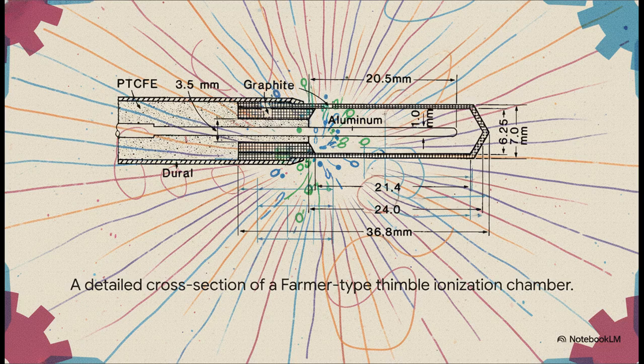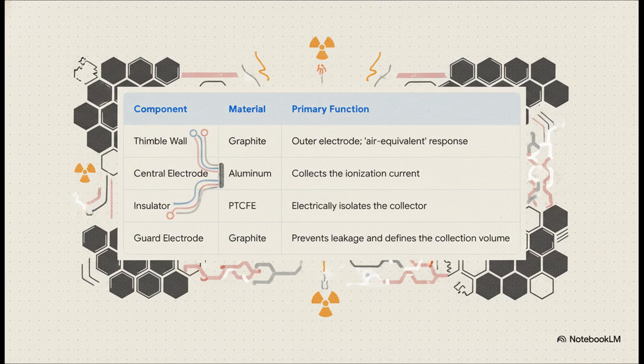And here it is. This is a classic farmer-type thimble chamber. You'll find these in hospitals all over the world, and it's a perfect example of everything we've just talked about. You can see all the parts: the outer wall, or the thimble, the central collecting electrode made of aluminum, and then nestled right in between, the crucial insulator and guard electrode assembly that makes the whole thing work. So let's do a quick rundown. You've got the thimble wall, usually made of graphite because it's air equivalent. It responds to radiation just like air does. Then there's the central electrode, made of aluminum, designed purely to collect that tiny, tiny current. The insulator, often a special plastic, provides that critical electrical separation. And of course, the guard electrode, doing its two vital jobs, blocking leakage and defining that collection volume with absolute precision.